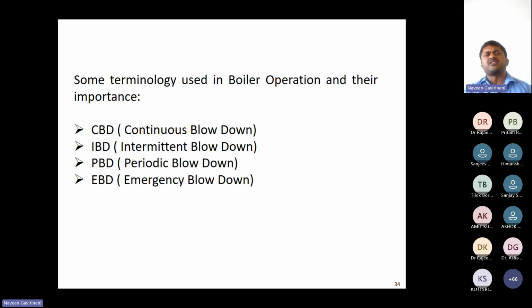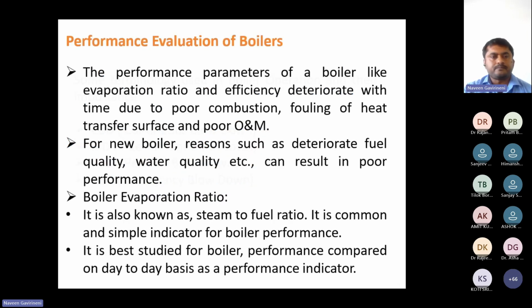Intermittent blowdown: if any parameter deviation happens beyond the design limit, we give this IBD, PBD. Emergency blowdown: if these three blowdowns are not working, we give the emergency blowdown for saving the unit. So this is the performance evaluation.